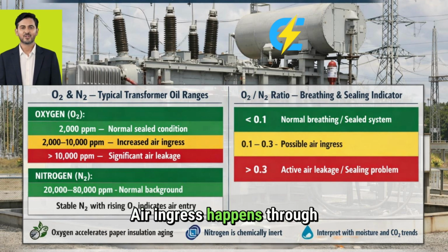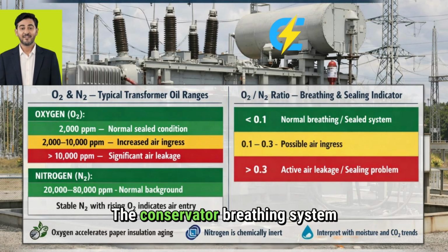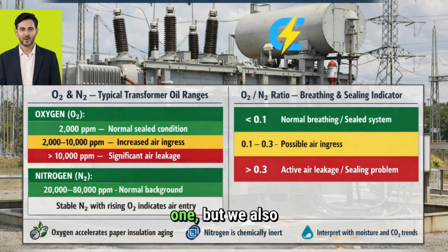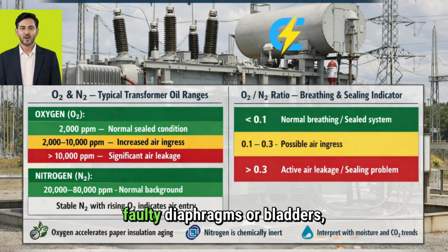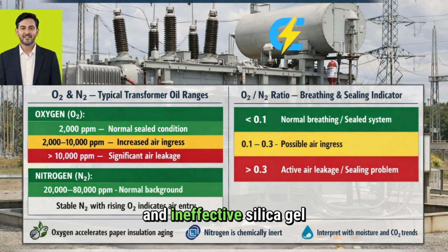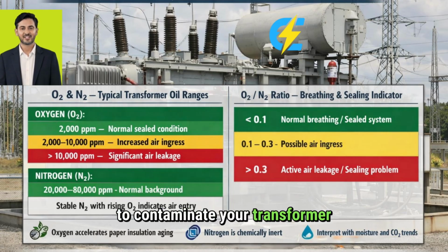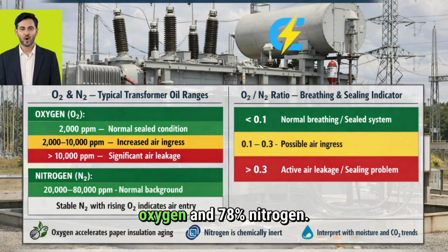Air ingress happens through several pathways. The conservator breathing system is the most obvious one. But we also see it through leaks in gaskets and seals, faulty diaphragms or bladders, and ineffective silica gel breathers. Each of these entry points allows atmospheric air to contaminate your transformer oil. The composition of this air is roughly 21% oxygen and 78% nitrogen.